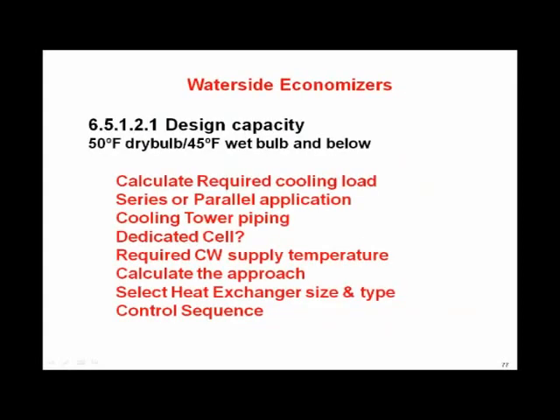So how do you do a waterside economizer? What are the things you need to be aware of? Calculate your cooling load. You've got your points to work on: 50-degree dry bulb, 45-degree wet bulb. You're going to put them in series or parallel. I think you've got to go series integrate. Maybe you can figure parallel out, but I think it's going to be series. Your decision. Cooling tower pipe: one or two sets of pipes. You're going to have a dedicated cell.